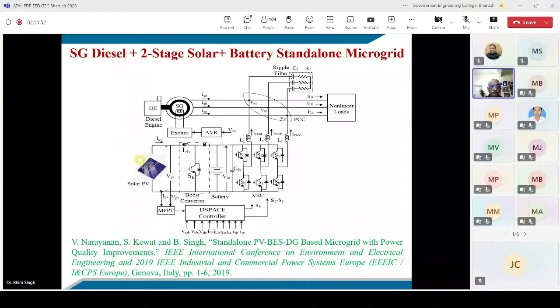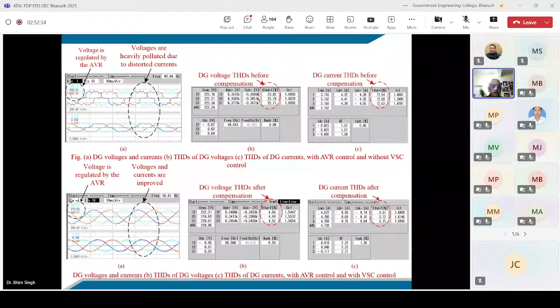And this was the typical control, even with a non-linear load, and the control for the generator also with the AVR and all that, again for isolated mode. You can understand how the voltage was distorted with the non-linear load, but when we switch on the converter, the THD of the voltage reduced to less than 5%. When you put a non-linear load on a DG set, it really distorts the terminal voltage, because a synchronous generator has a very large synchronous reactance. If you draw harmonic current from it, the drop will be much larger than with the grid. The grid does not have as much source impedance as a conventional synchronous generator. So once we put in the converter with compensation, the terminal voltage THD reduces to less than 5%, and the DG set current THD also reduces.